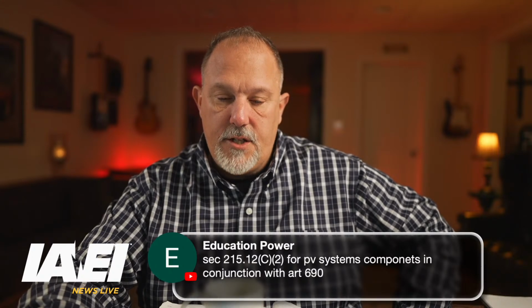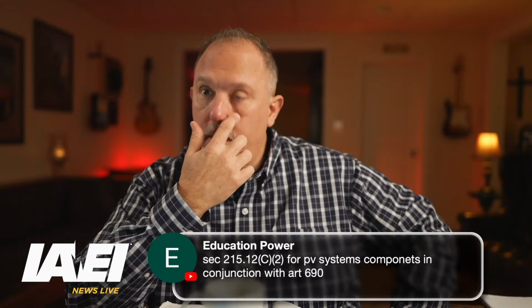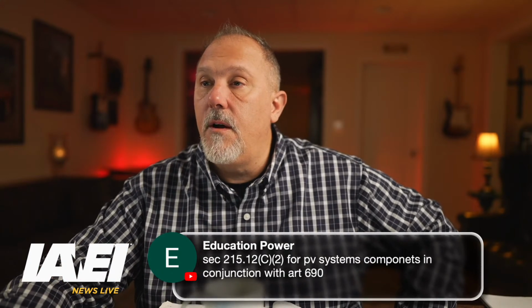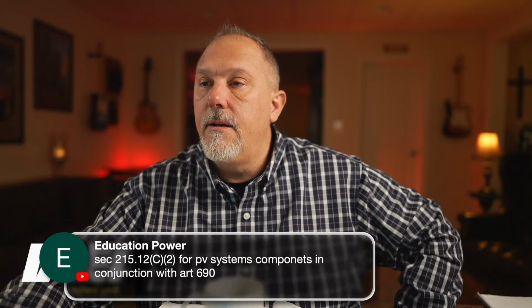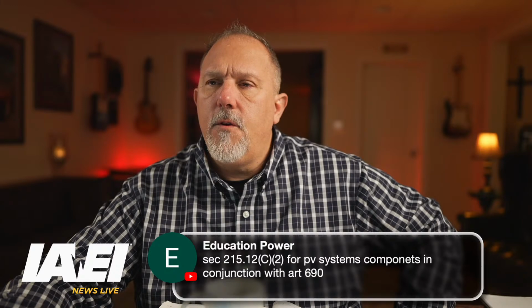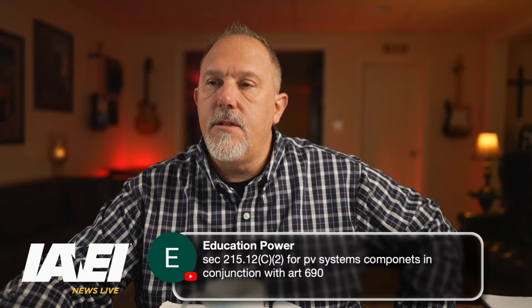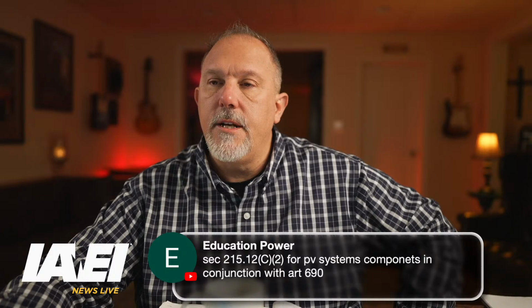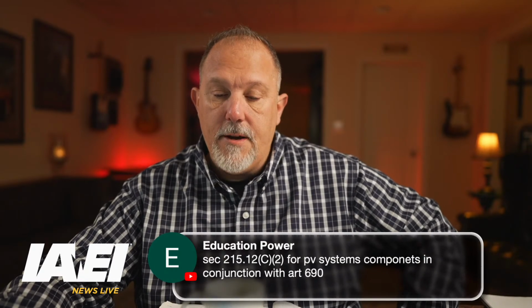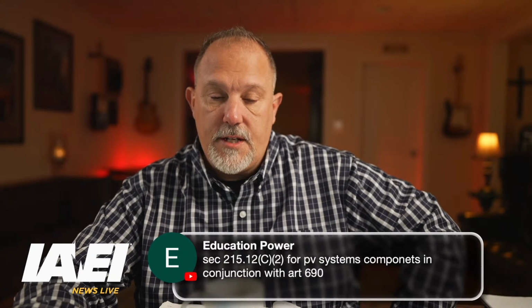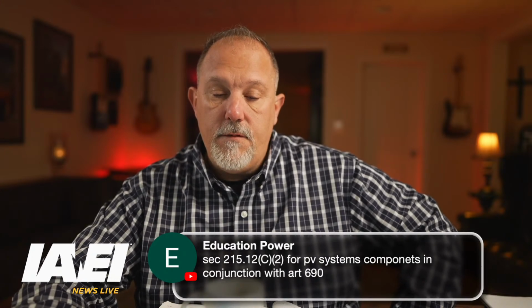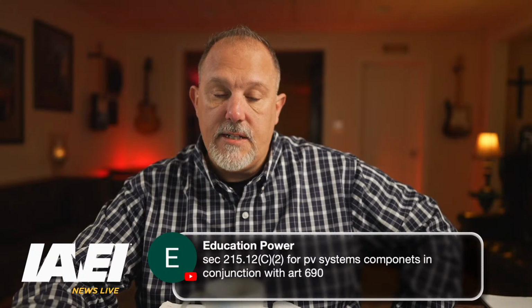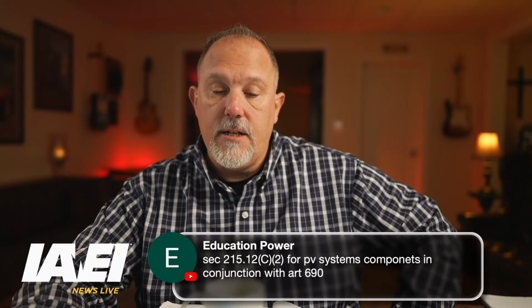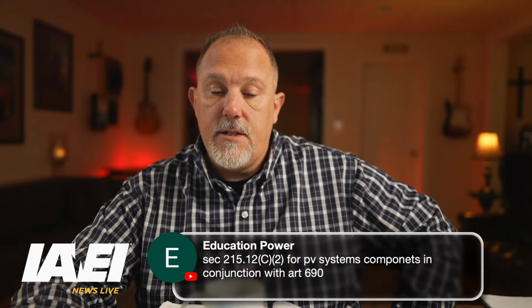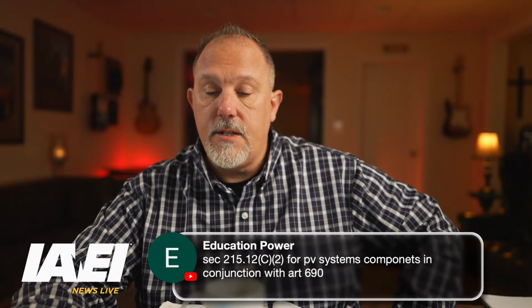Identification C2. I'm not sure what that's in response to, Robert. That's 215.9, for PV system components in conjunction with Article 690. All right. Yep, we haven't gotten there, but 215.12(C)(2). 215.12 is identification, and C is identification of ungrounded conductors, and 2 is feeders supplied from direct current systems.